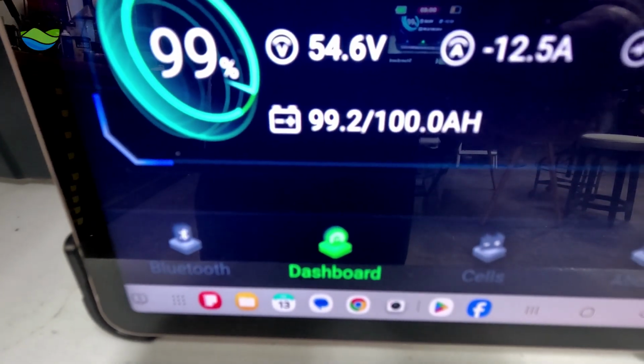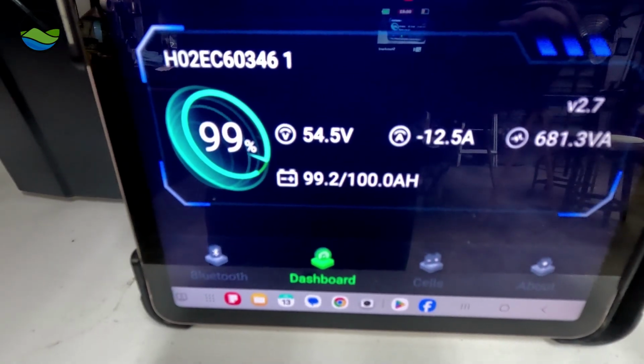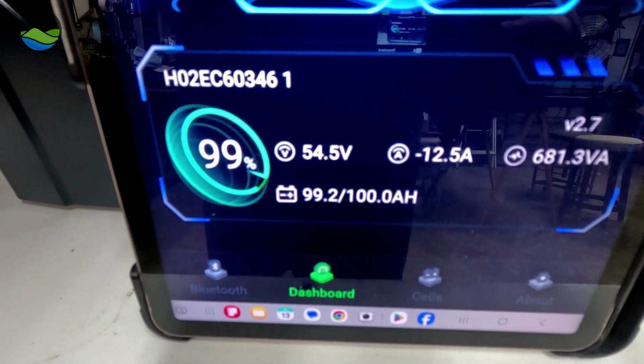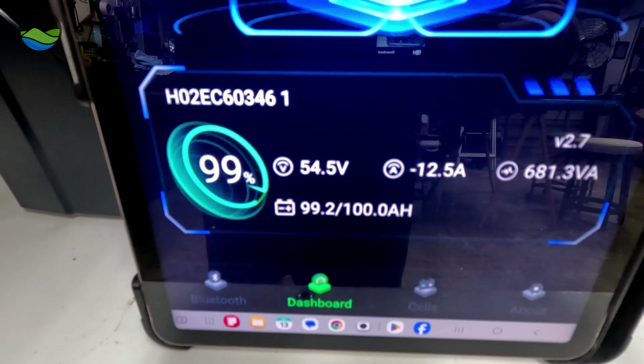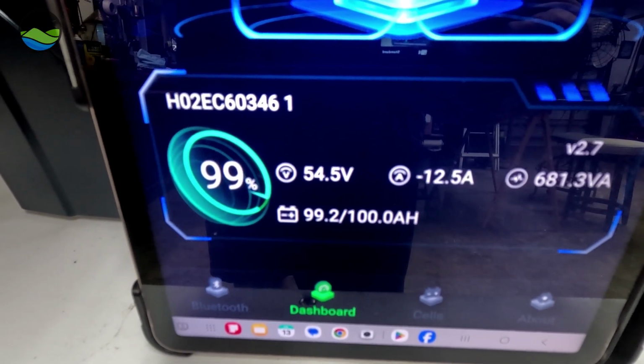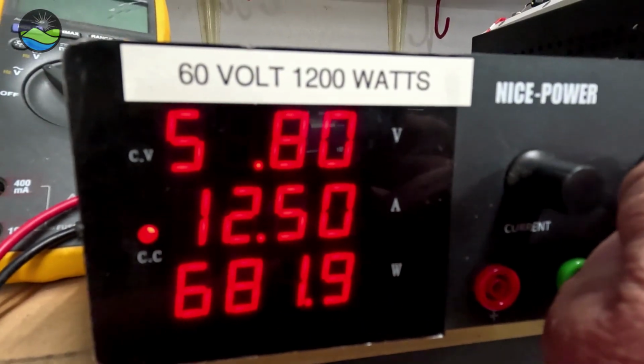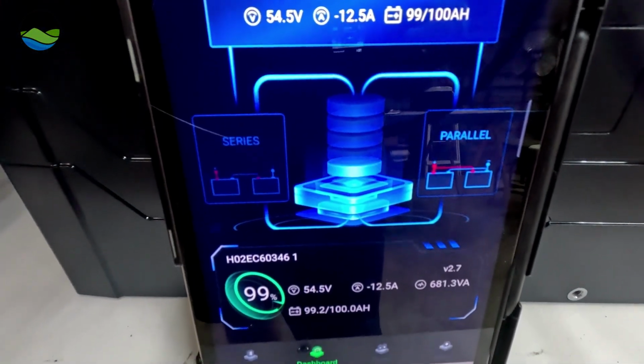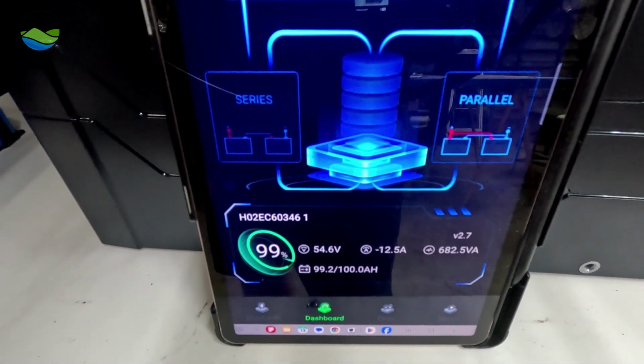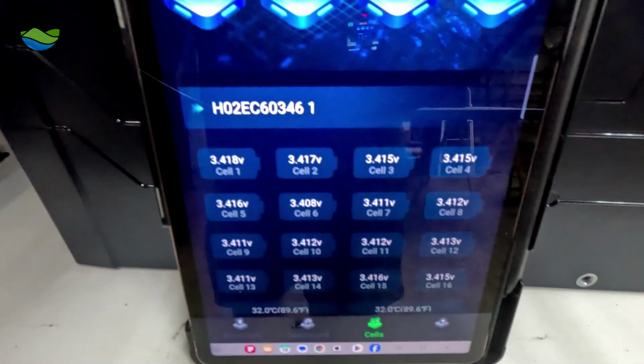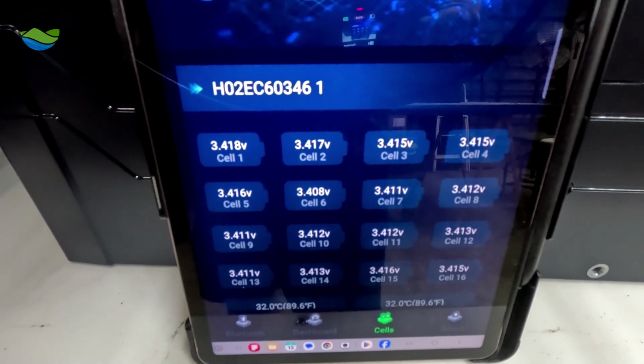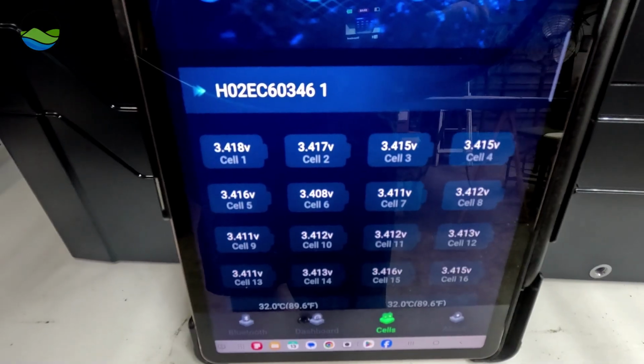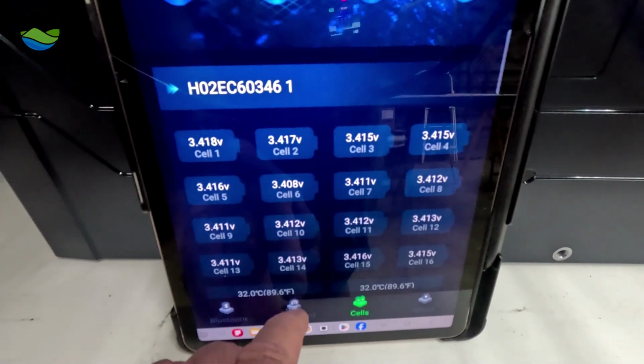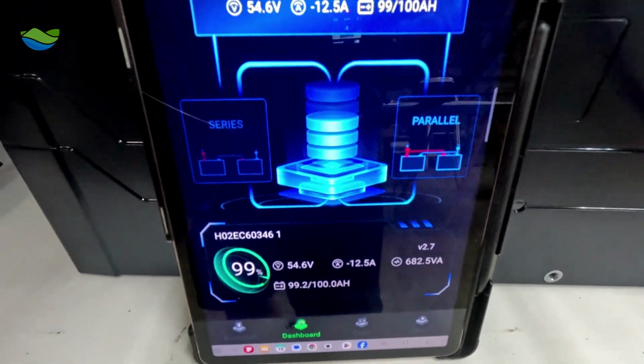You can see on the app there it says 99.2. So when this gets up around 99.5, 99.7, that voltage will start to climb pretty rapidly. Up to 56.8 is what our target is, because I think that's what we have here. Let me see. Yeah, we've got 56.8 as our target, and that's in the middle of the upper knee. That's not the upper knee. 3.65 volts per cell would be the top of the upper knee. We don't need to go there, especially on the very first charge. So, alright, we'll come back here when it gets a little bit more full.